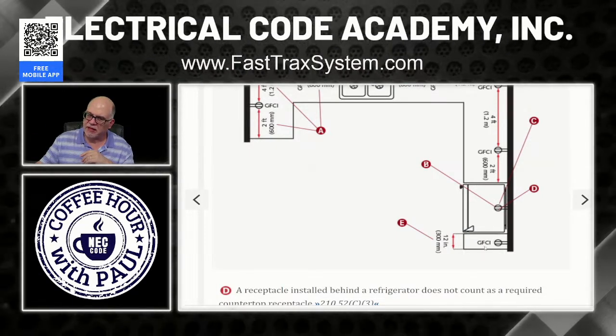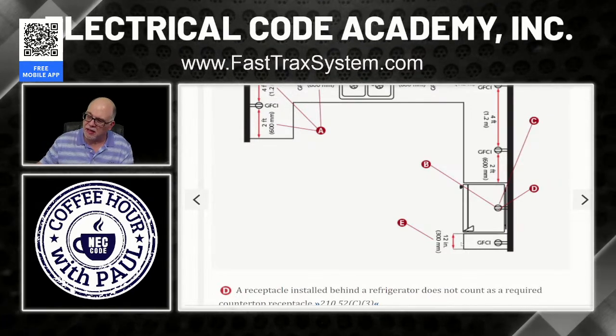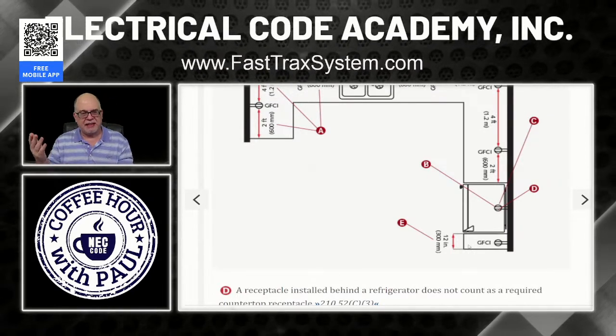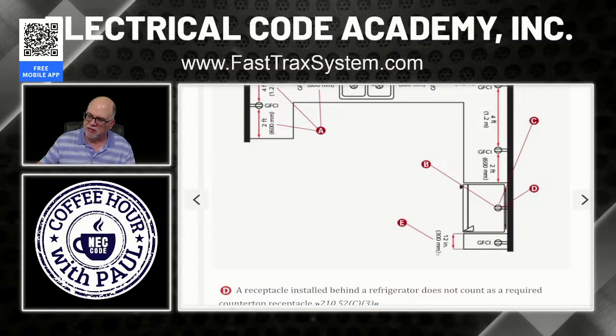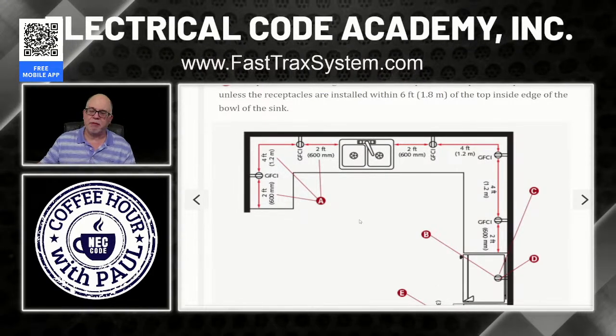And then this piece of counter right here is at least 12 inches. Now, if this had been less than 12 inches, then I wouldn't need anything there. But this is 12 inches as it shows here on the diagram. So I have to have a receptacle here. All of these receptacles serving the countertop have to be GFCI protected.